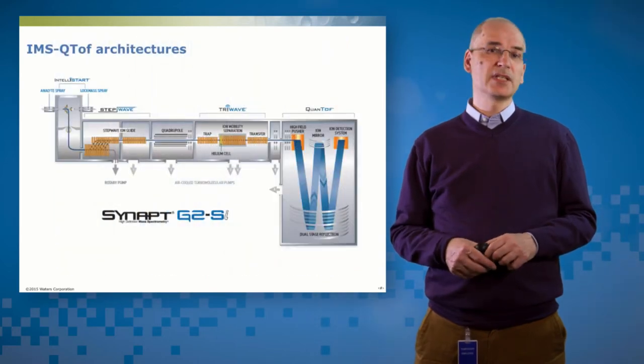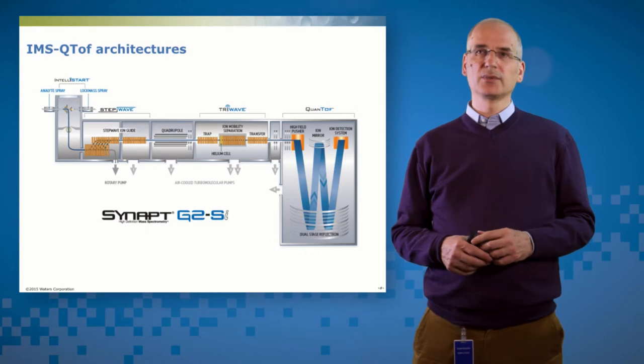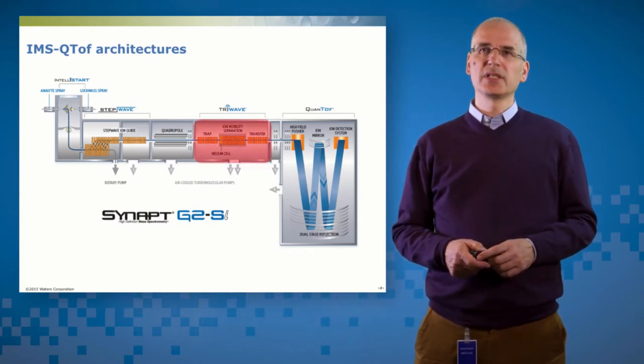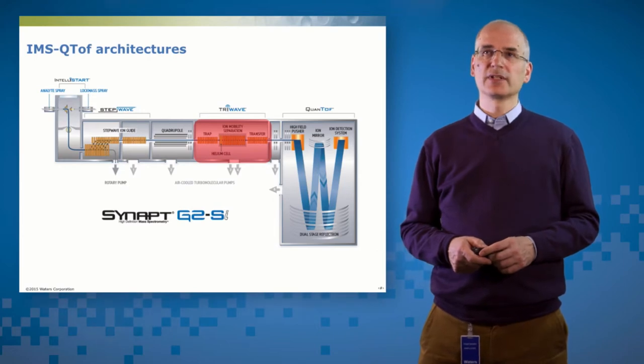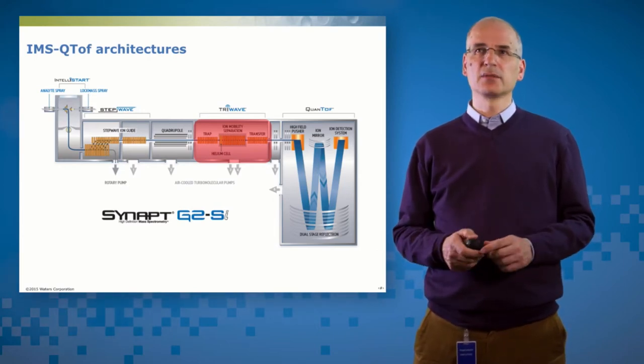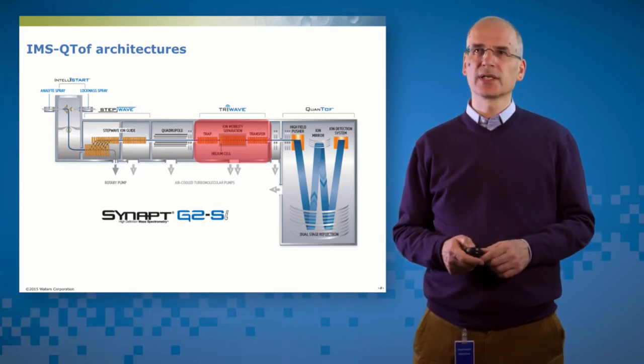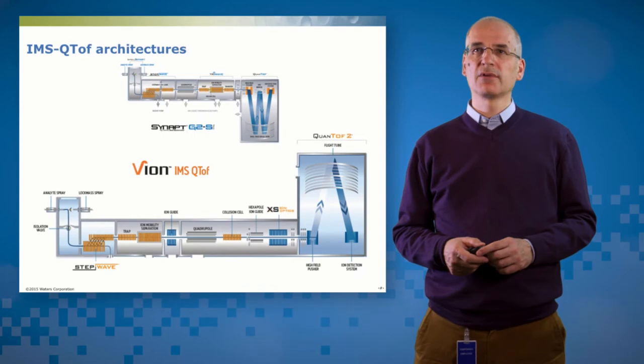So the ability to do these kinds of experiments has been around for a while with the Synapt family of products. And in the Synapt family of products, the ion mobility separation is in the centre of the instrument in the tri-wave. And it's bracketed by two independent collision cells, one before and one after.